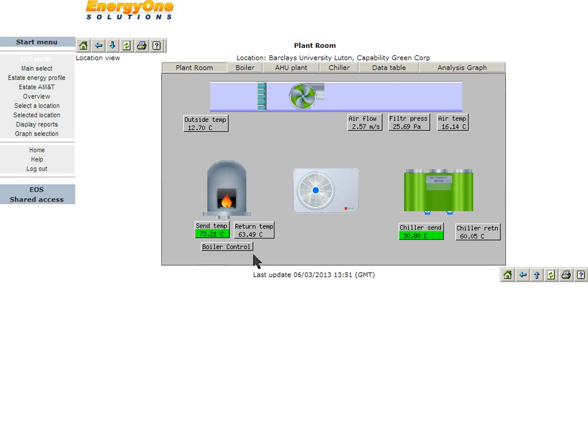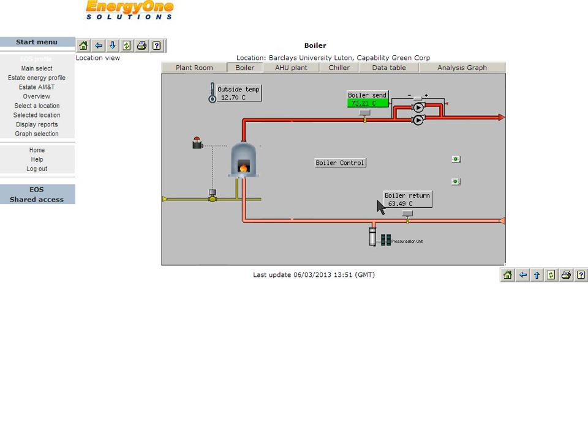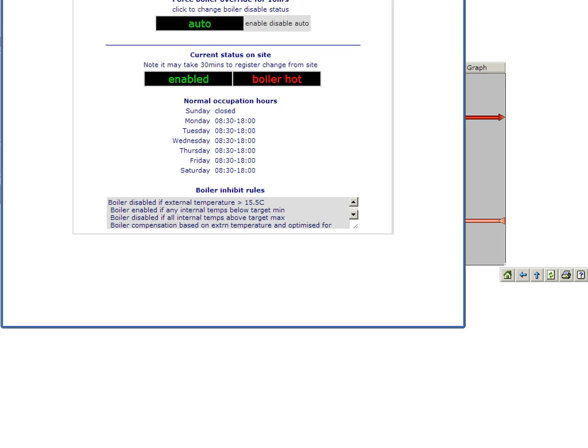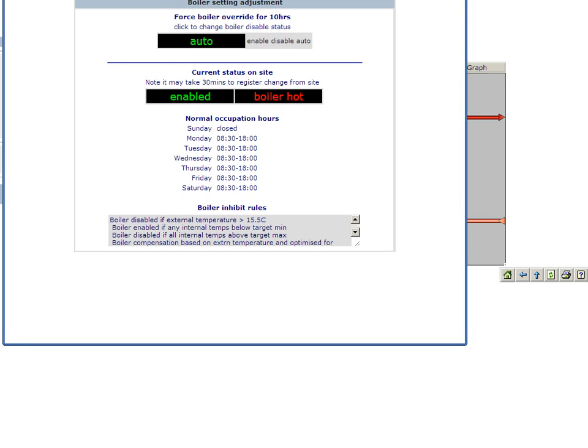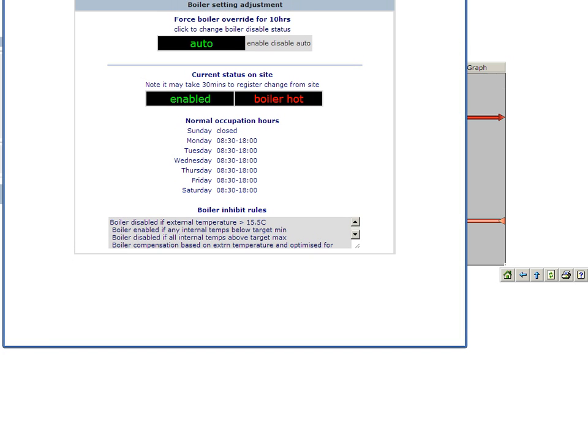At a glance, we can see the boiler flow and return temperatures, the same for the chiller, and we can see if the air handling system is operational. By selecting boiler, we can now see in more detail the flow and return, pump selectors, and outside and return temperatures. We can also select the Boiler Control tab to demonstrate the plant rules. It is at this point where the rules are configured for the operation of the heating and cooling plant.